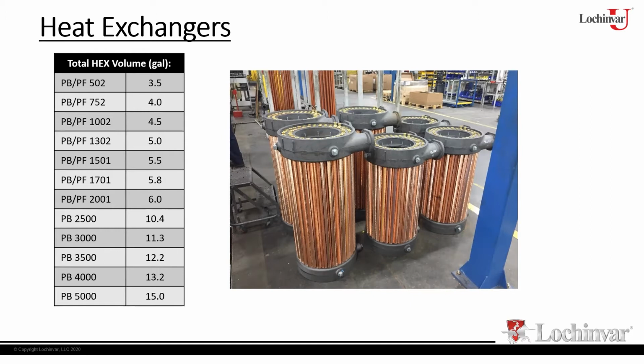Because of the low mass design, the flow is critical to the heat exchanger's operation and to its life. So that means piping comes into play. With low mass heat exchangers, you must pipe these primary, secondary. There is no full flow option here. So it has to be primary, secondary in a hydronic heating application. If it's being used as a potable water heater, where your smaller models can be sold as water heaters, then it has to be piped directly to a storage tank or tanks at that point. So again, we have very specific flow rates that we want to look at, and those are all listed in the installation manuals for the products.